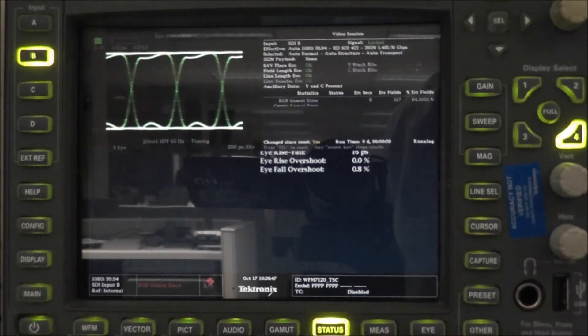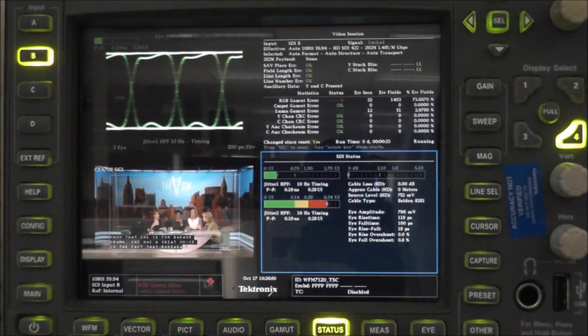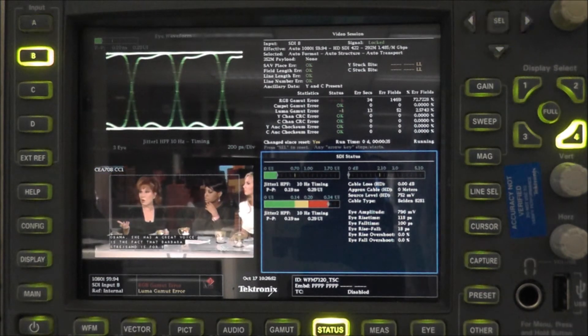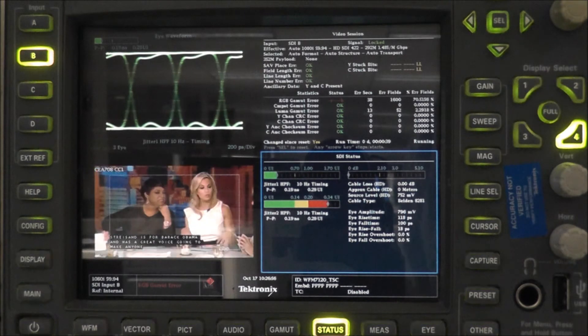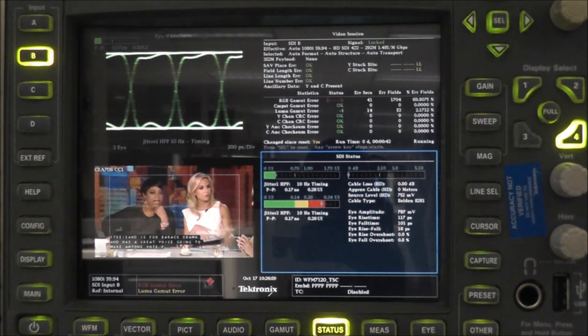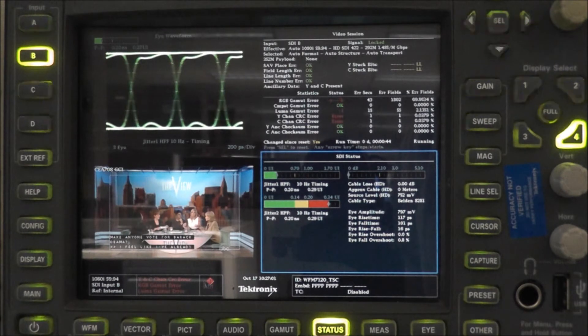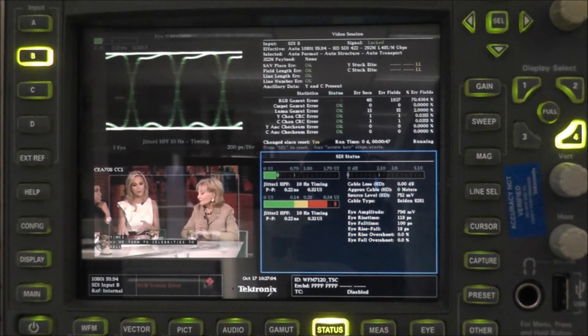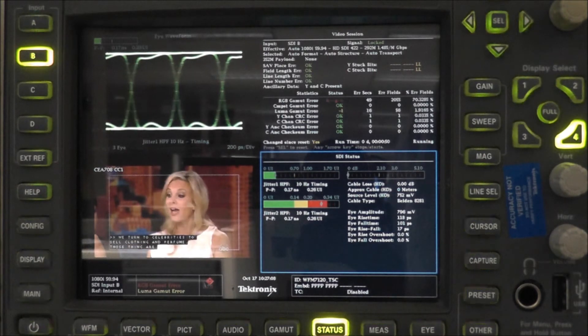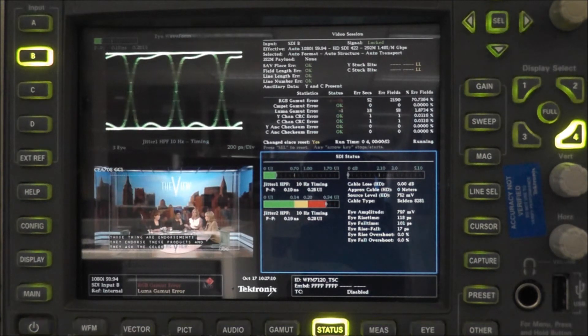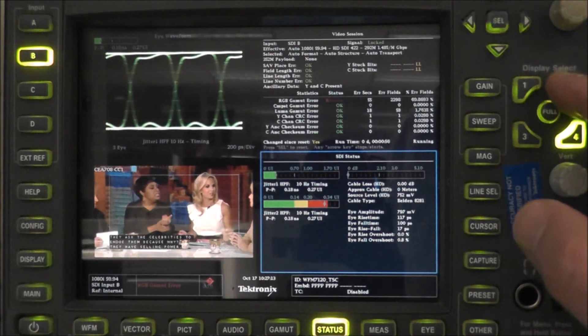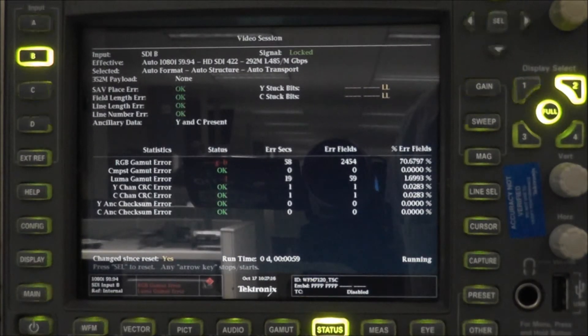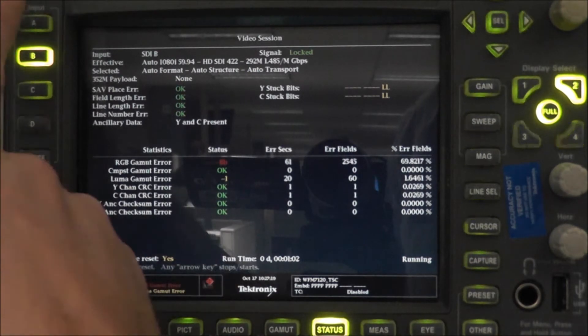When in the field, you do need a nice, firm, objective measurement. That way, one knows when they are on that edge of the digital clip. That is where our video session display can come in. From the video session display, we are able to calculate our CRC errors and the checksum errors. This display right here does show that.